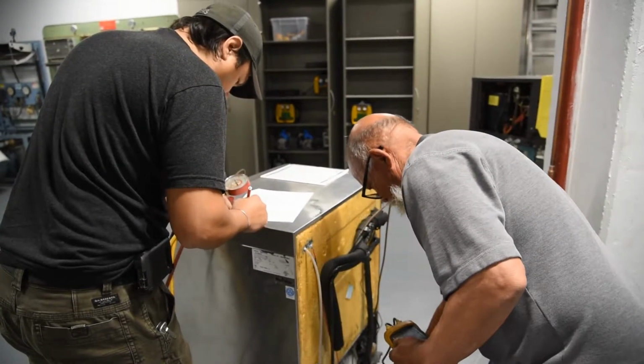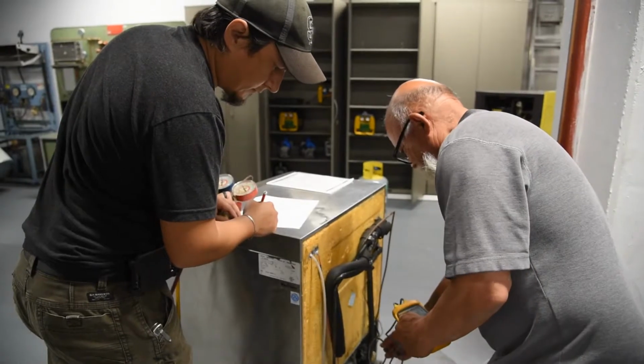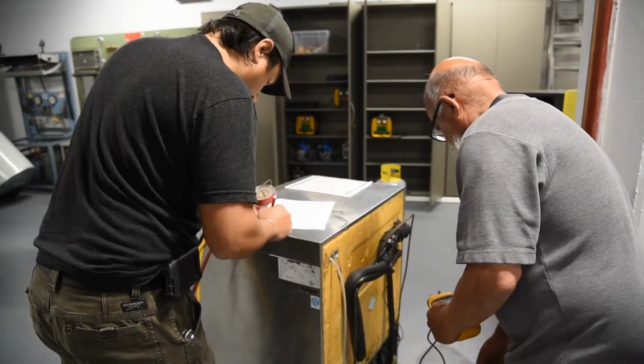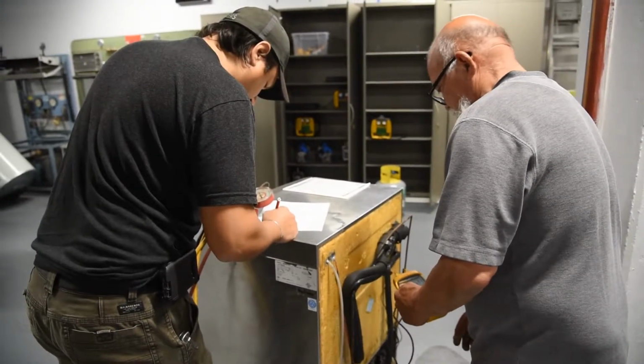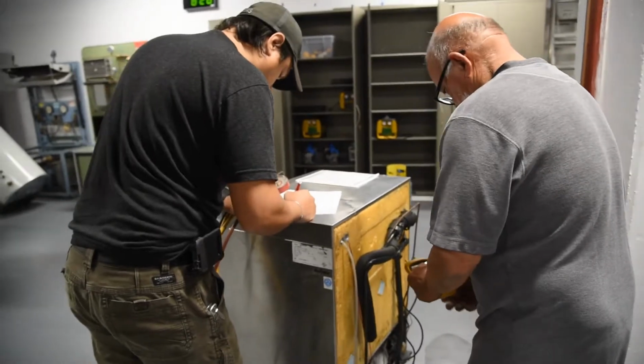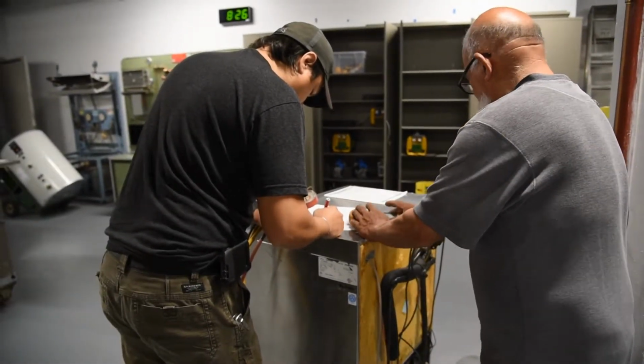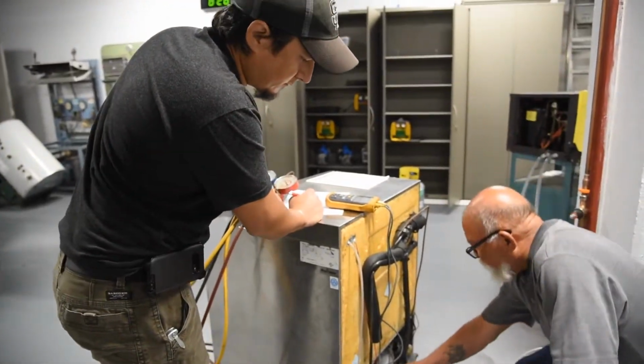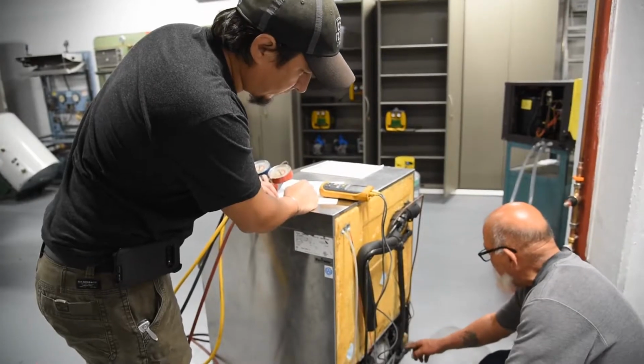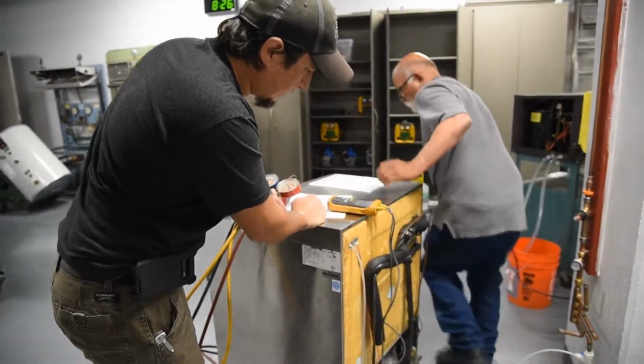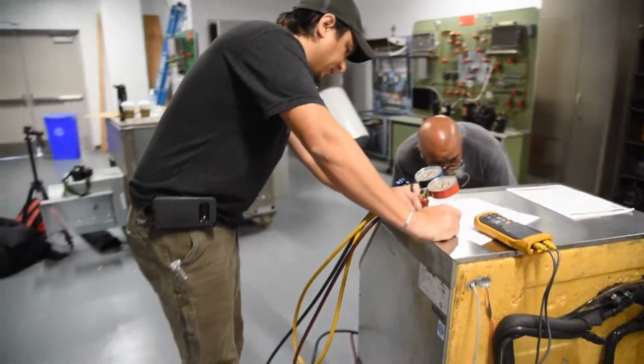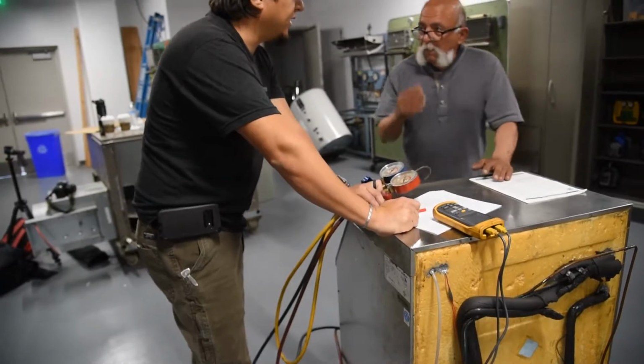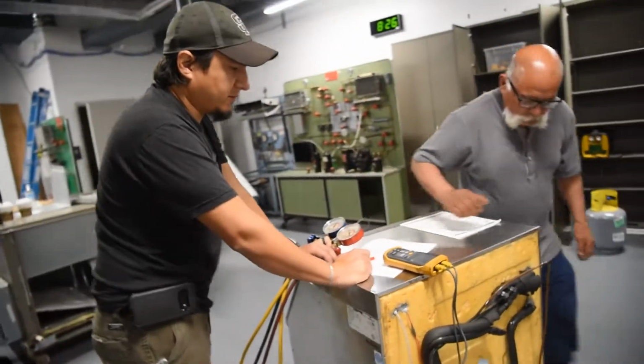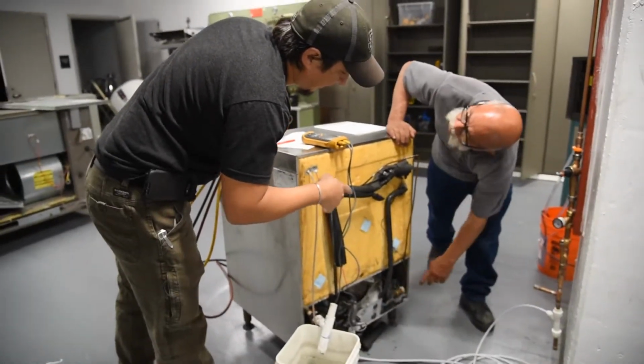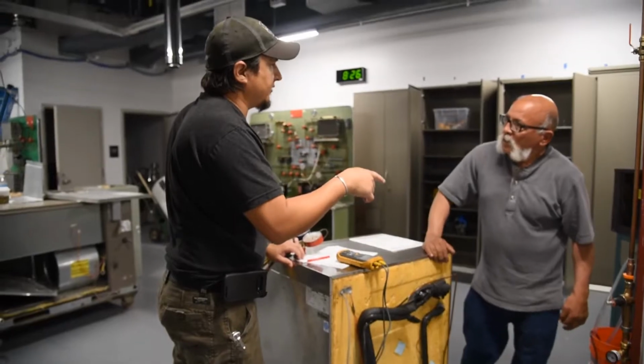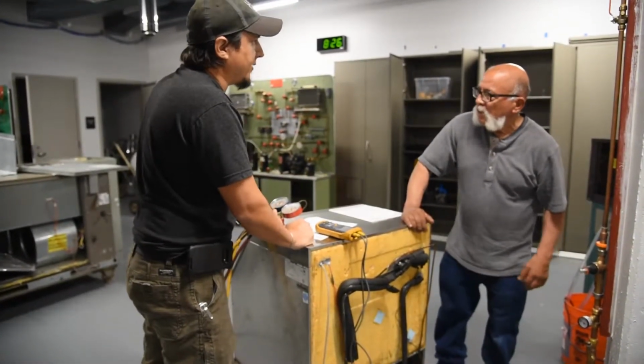No, excuse me. The hot gas line, hot gas tubing, 76 degrees. The liquid line, 60 degrees. What happens is we have hot gas coming from the compressor, going into the evaporator, and melting the ice off of the evaporator. That is a hot gas bypass, right? Yes. And it's bypassing the TXV, correct? Yes. So instead of going to the condenser, it's bypassing the condenser, bypassing the TXV, and shooting hot gas into the evaporator.